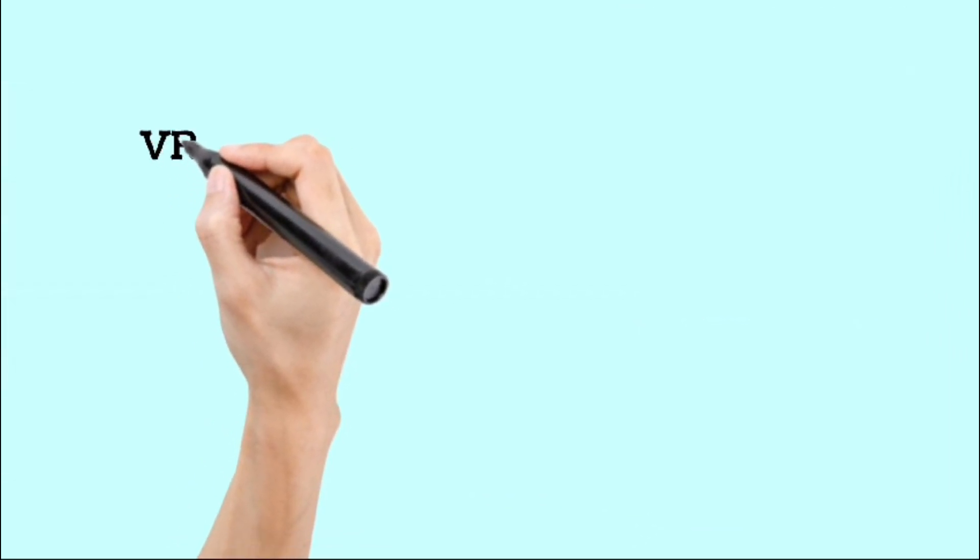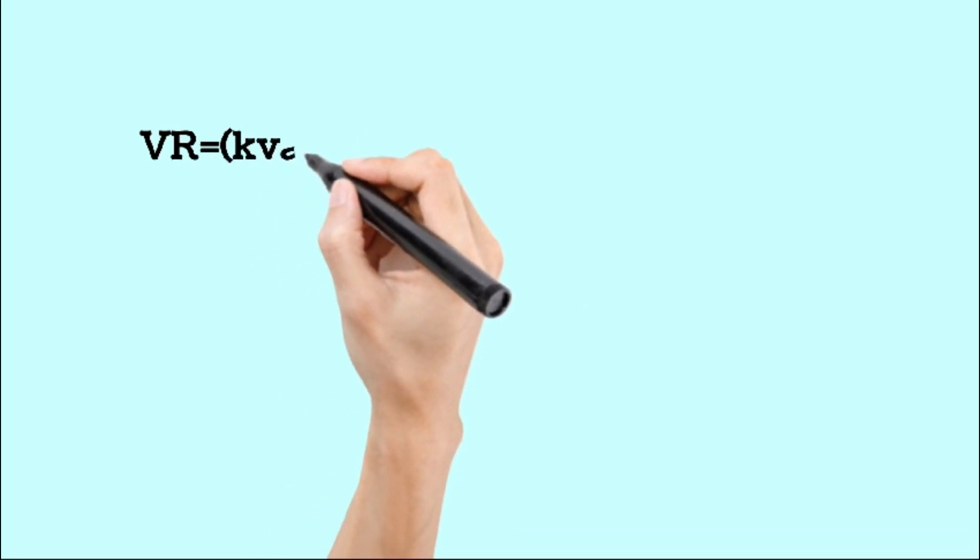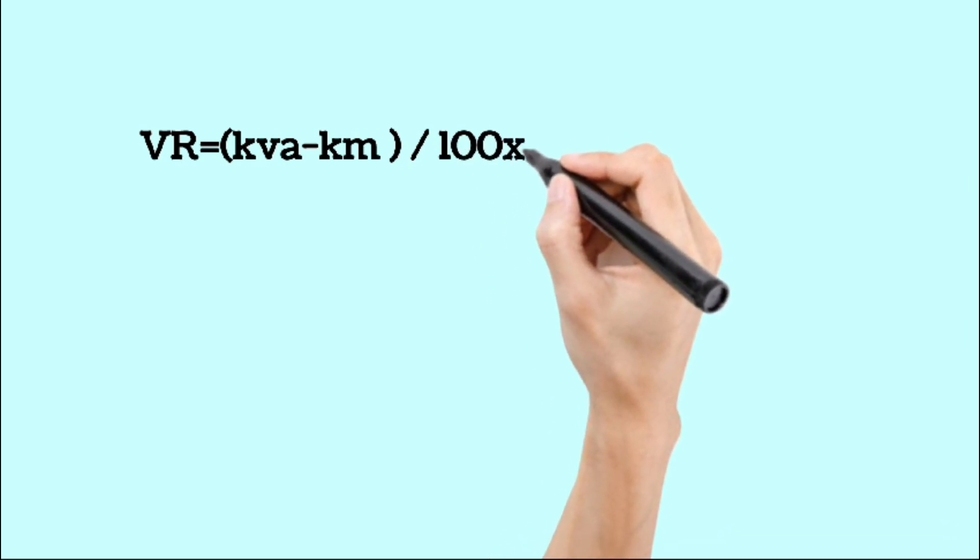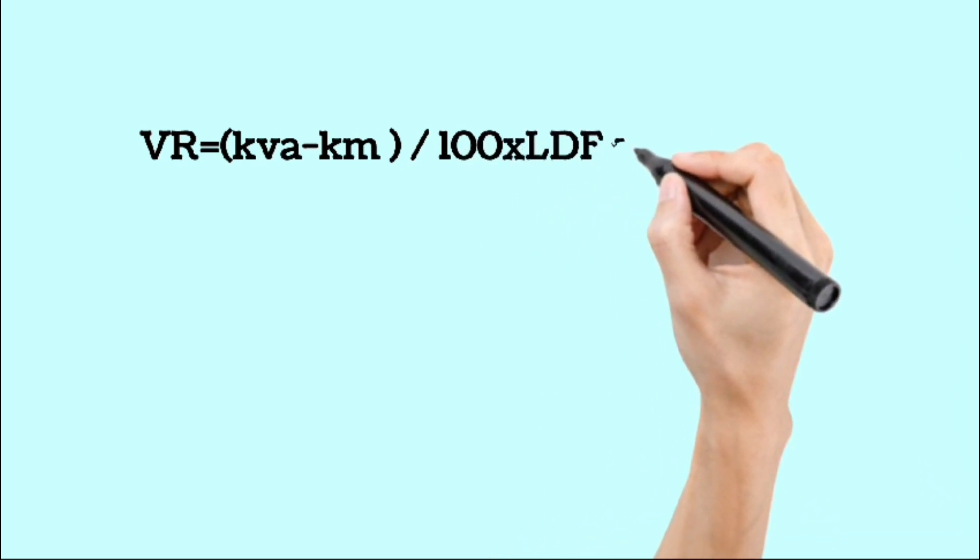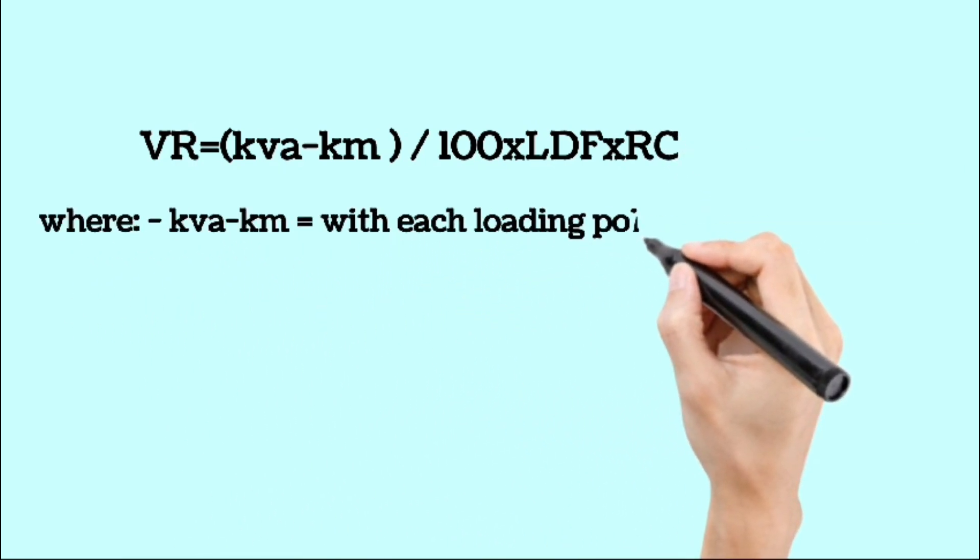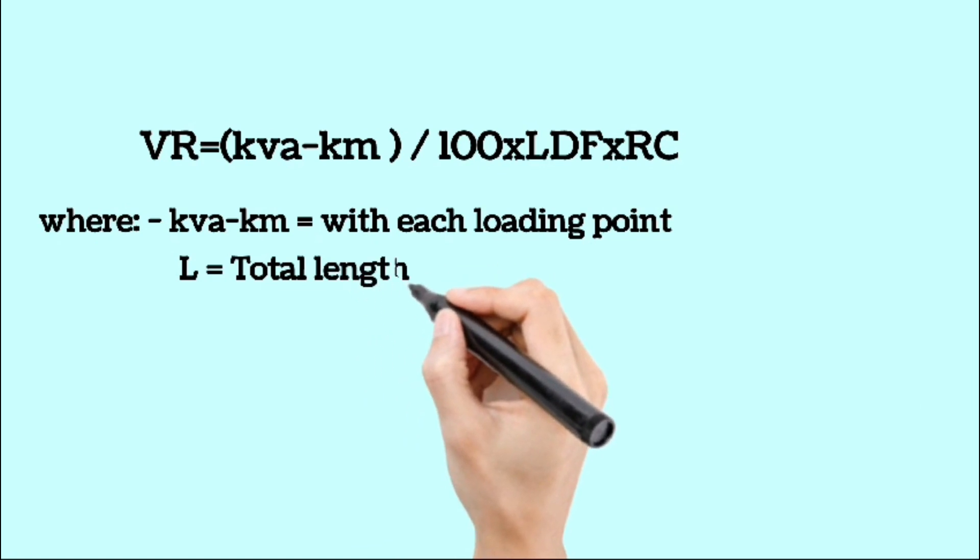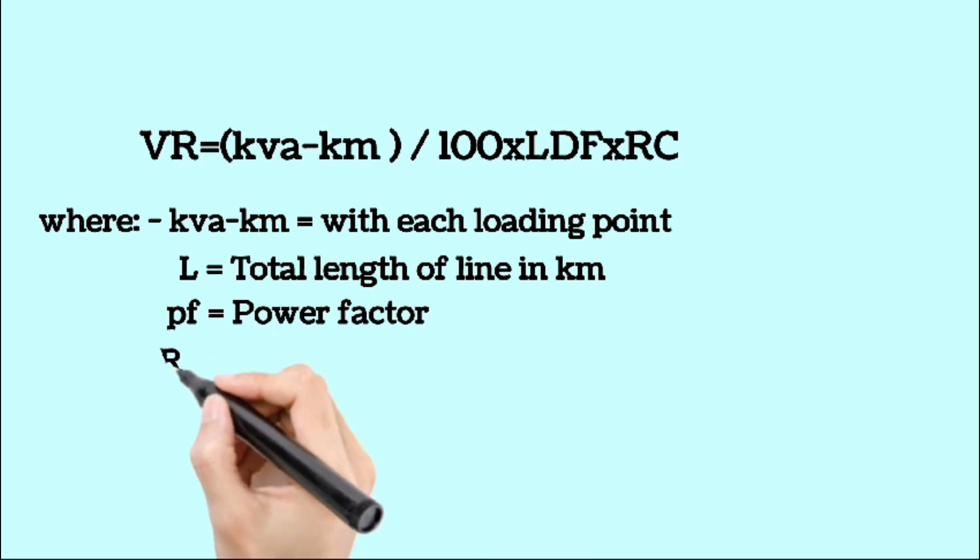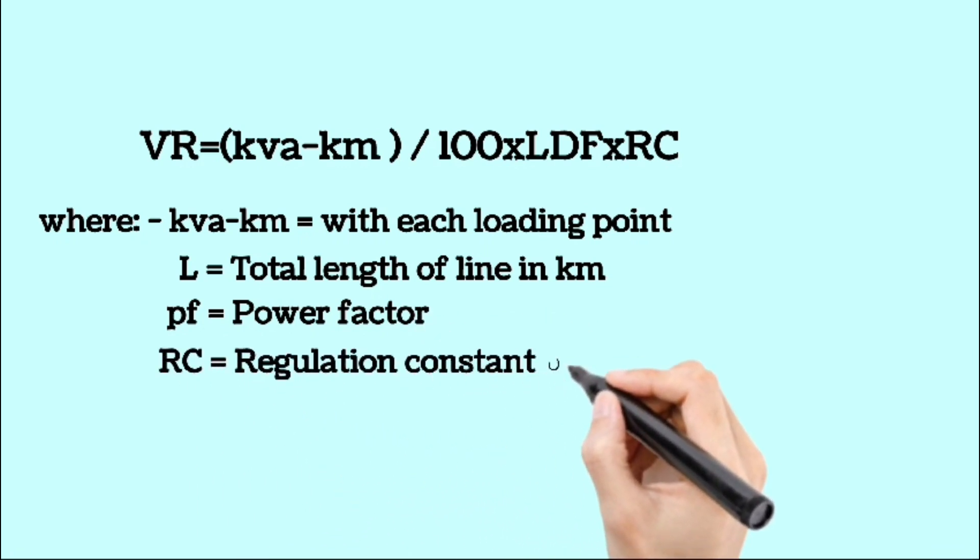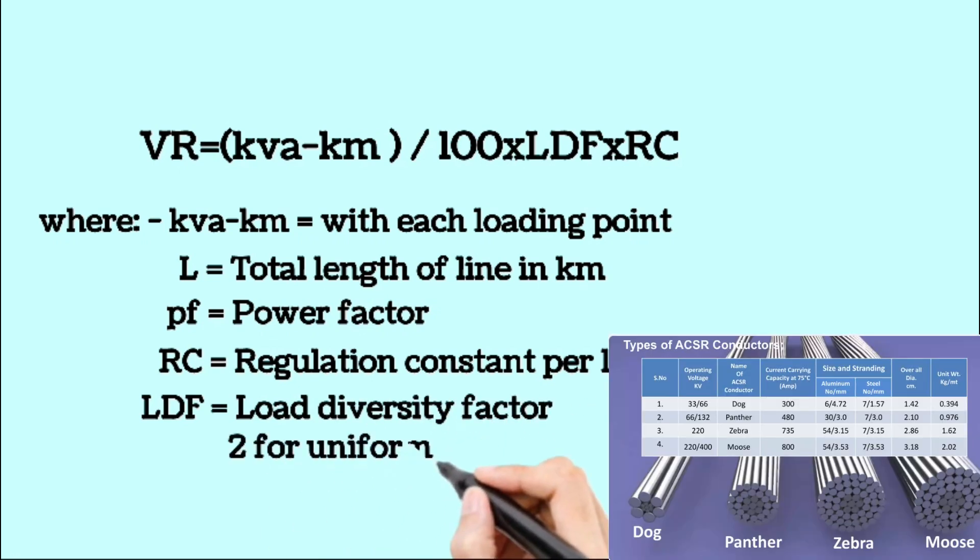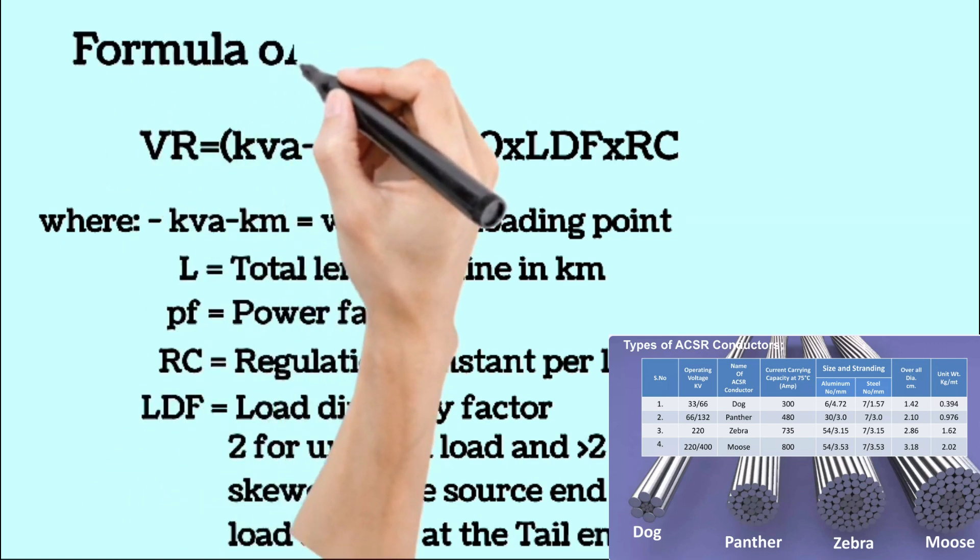Now let's look at the voltage regulation formula. Remember this for future reference: voltage regulation equals kVA kilometer divided by the product of 100 and load diversity factor and regulation constant. Here we will explain each abbreviation one by one. Feel free to take a screenshot for better understanding and reference. Please note that the regulation constant depends on the current carrying capacity of the conductor and the length of the line. It is always measured per 100 kVA kilometer.